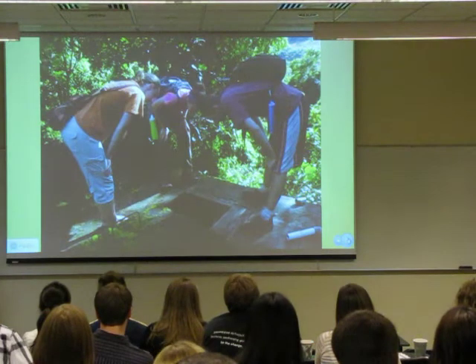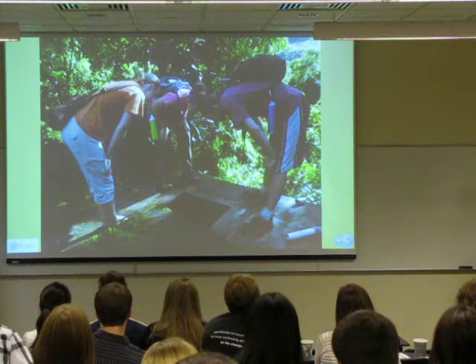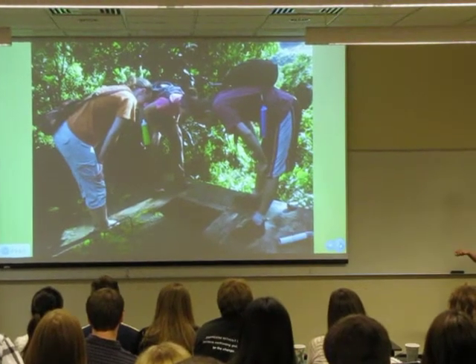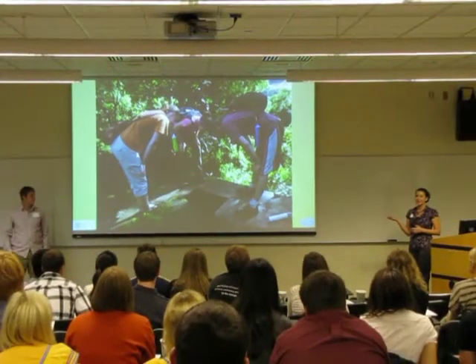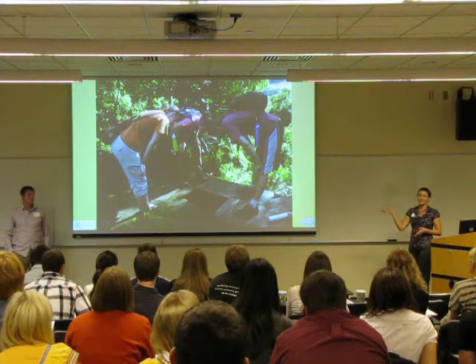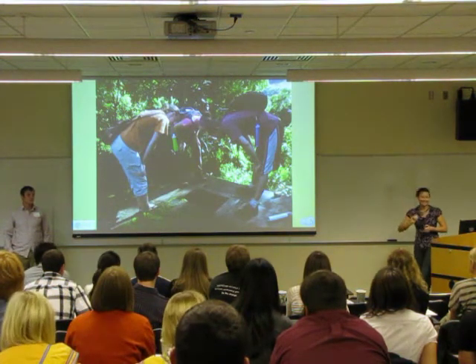From this natural spring source, it feeds down by gravity into a water storage tank, which is about 6,000 gallons. From the get-go, this was supposed to serve the entire community, and it didn't because there were a few elevation changes that were too drastic to reach all the homes. The water storage tank also doesn't have protection on the inlet pipes, so we were looking at crabs in the storage tank, which is not ideal.